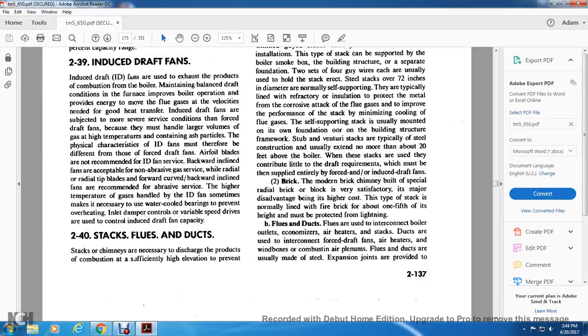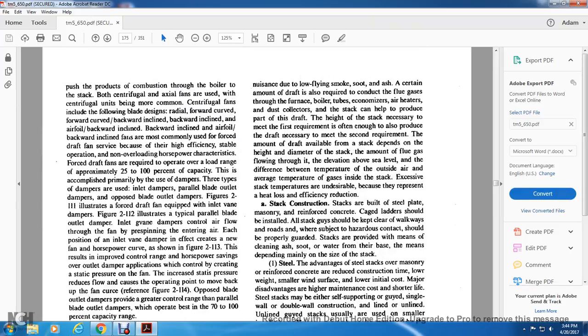240. Stacks and fuels, stack flues and ducts. Stacks and chimneys are necessary to discharge the products of combustion at a sufficiently high elevation to prevent nuisance due to low-flying smoke, soot, and ash. A certain amount of draft is required to conduct the flue gas through the furnace, the boiler's tubes, and the economizer, air heater, and dust collectors.